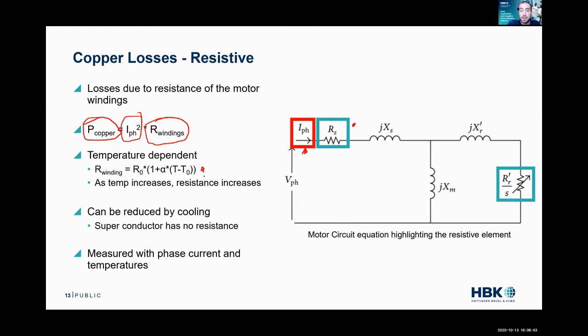So again in real time you can start taking this data and understanding your losses. Now your resistance model can really be as complex as you want. You can take a linear model and just say at 23 degrees my resistance is X, at 30 degrees my resistance is Y and draw a line through it. Just have a very linear resistance model.